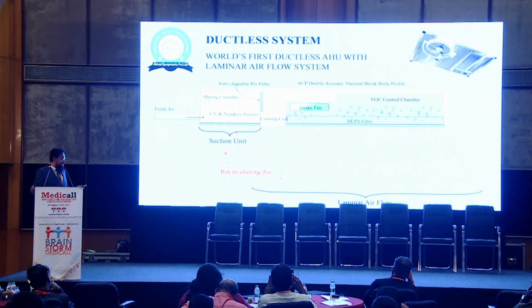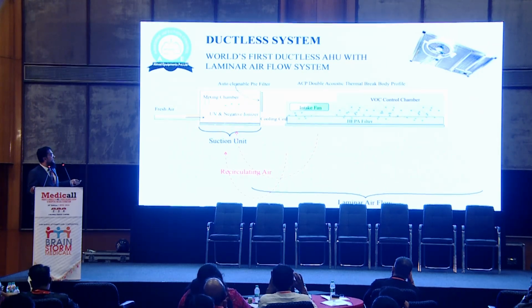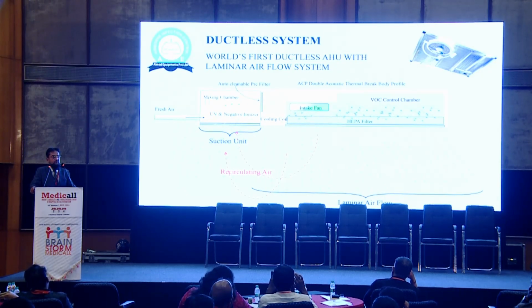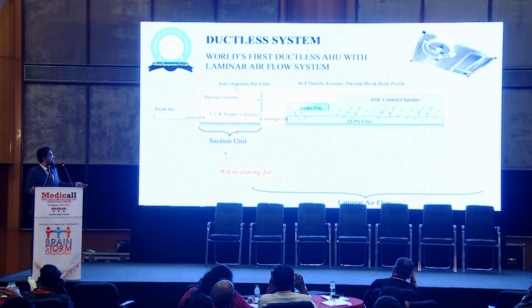So just to recall it again, fresh air coming in this area, this is the mixing chamber where the UV lights and the negative ionizers are. Here we are given the auto cleanable pre-filters, the pre-filter we are given before the cooling coil, and the one we are given near the fresh air damper. Then the cooling coil is there, then the backward curve fan. This is sucking the air from this area, and from this HEPA and the activated carbon filter, it will come on the table level. So this is the airflow pattern that is getting created with the system.